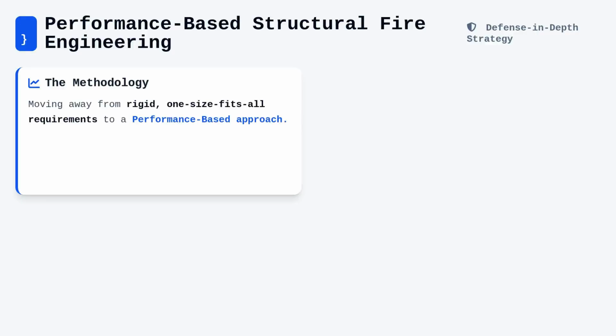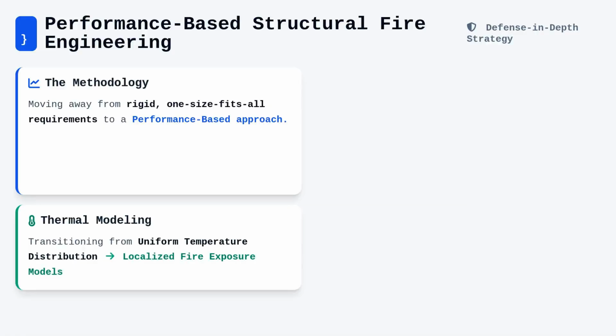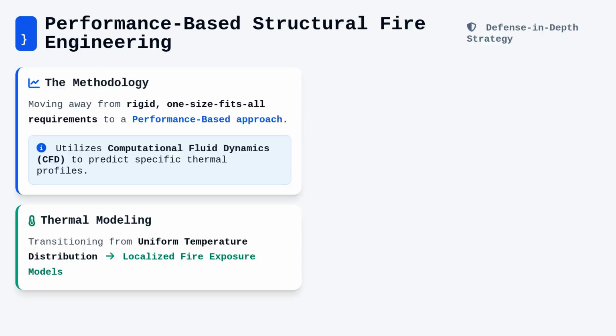When analyzing these buildings, we often employ performance-based structural fire engineering to move away from rigid, one-size-fits-all requirements. This requires an understanding of localized fire exposure models rather than assuming a uniform temperature distribution throughout the entire fire compartment. By utilizing computational fluid dynamics, we can predict the specific thermal profiles that will impinge upon the building frame, allowing us to estimate the actual versus the nominal fire resistance required to prevent collapse.